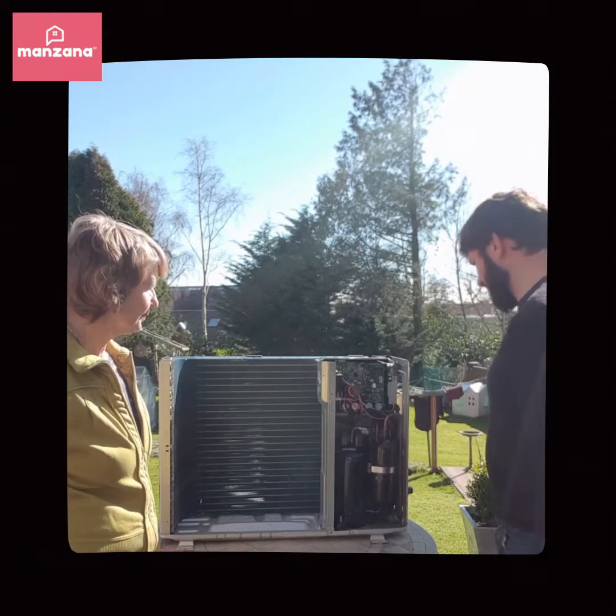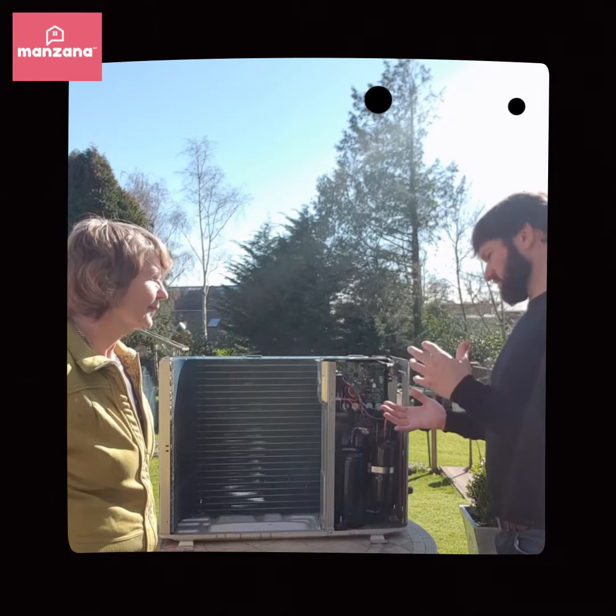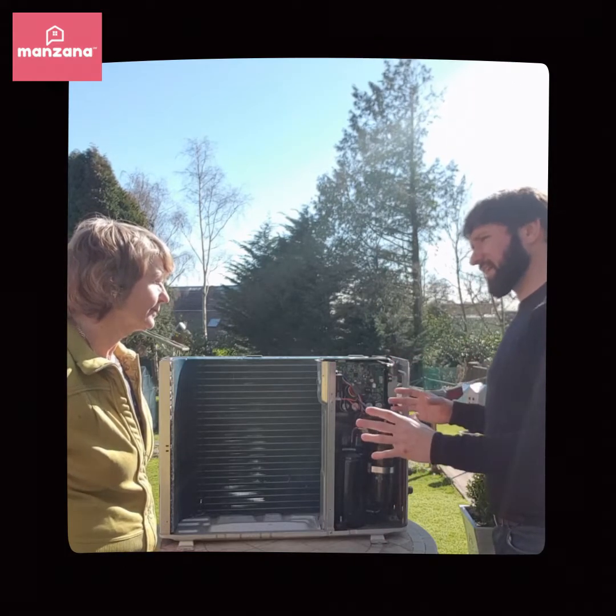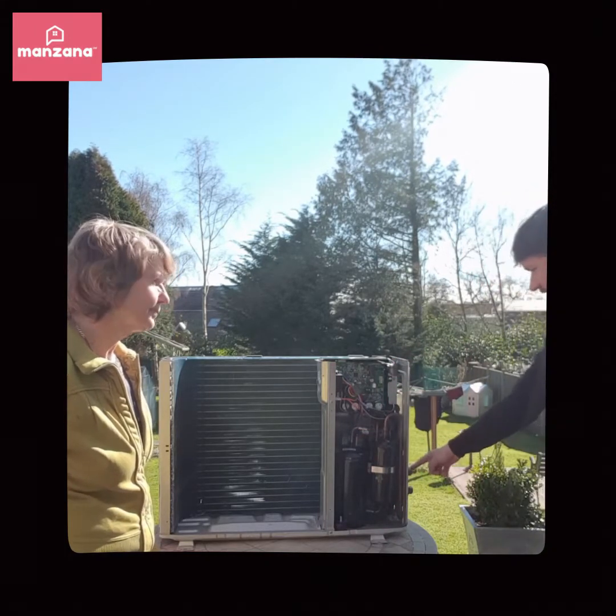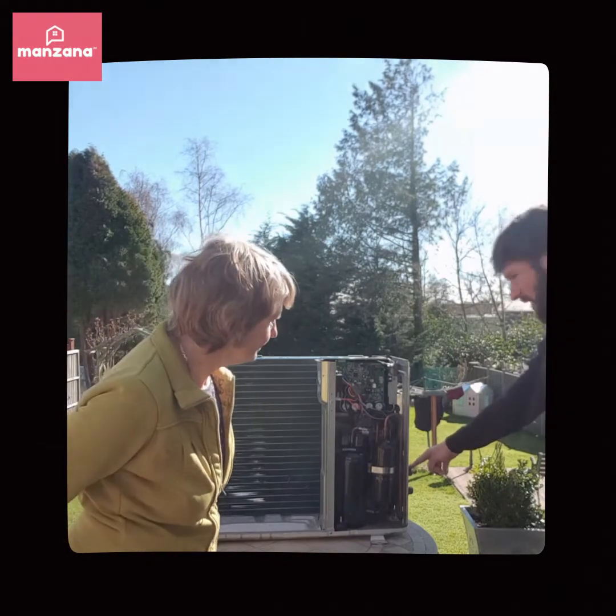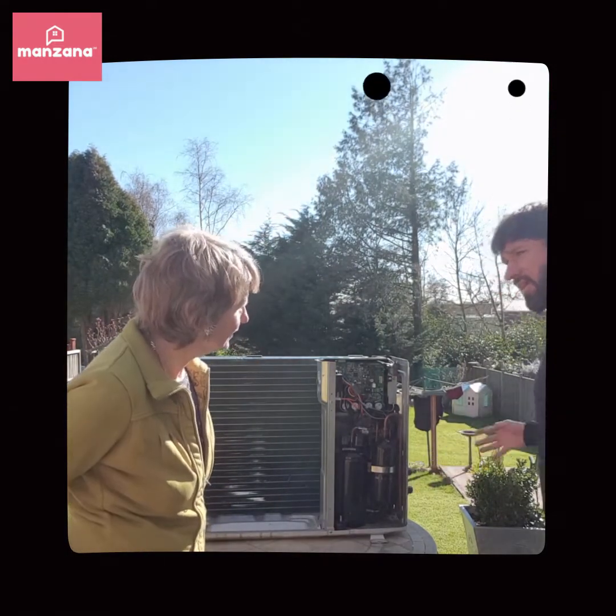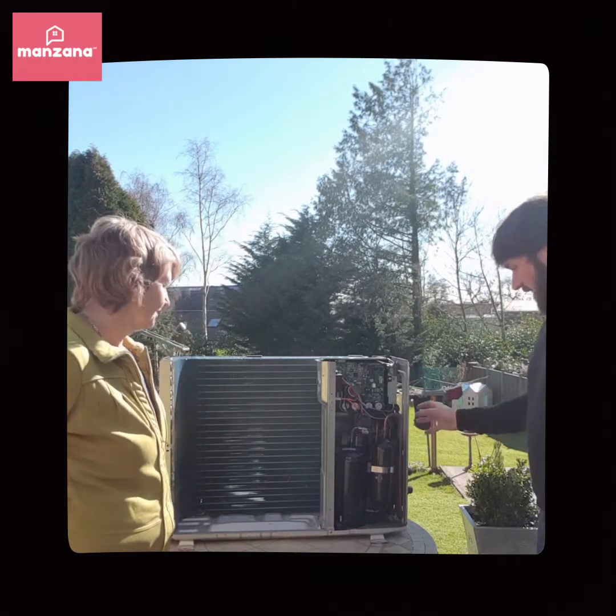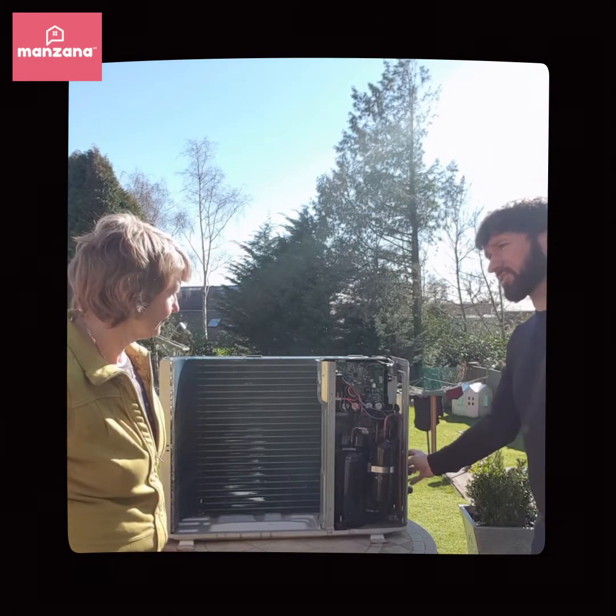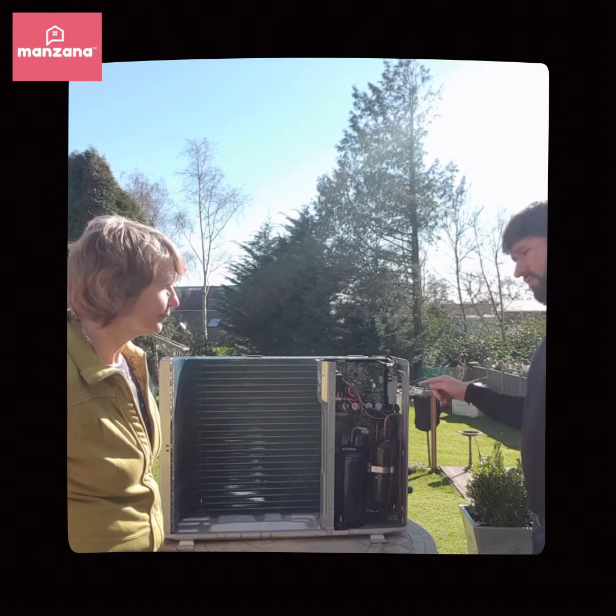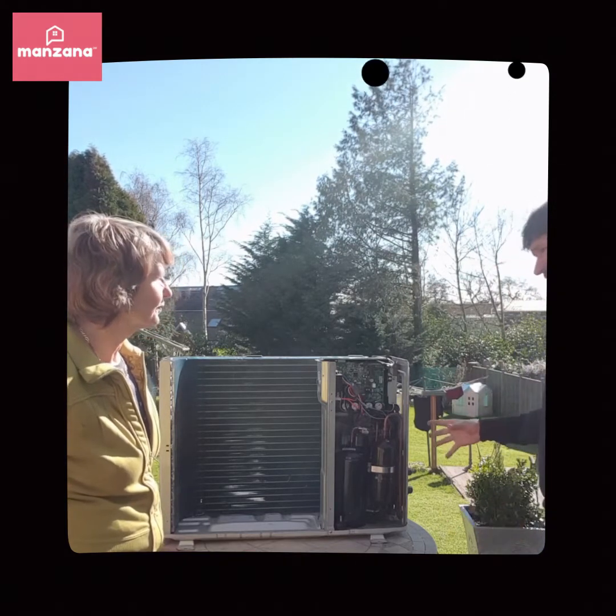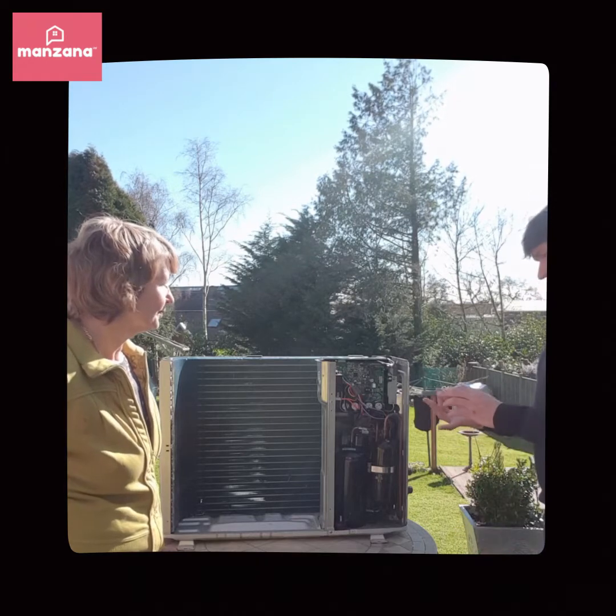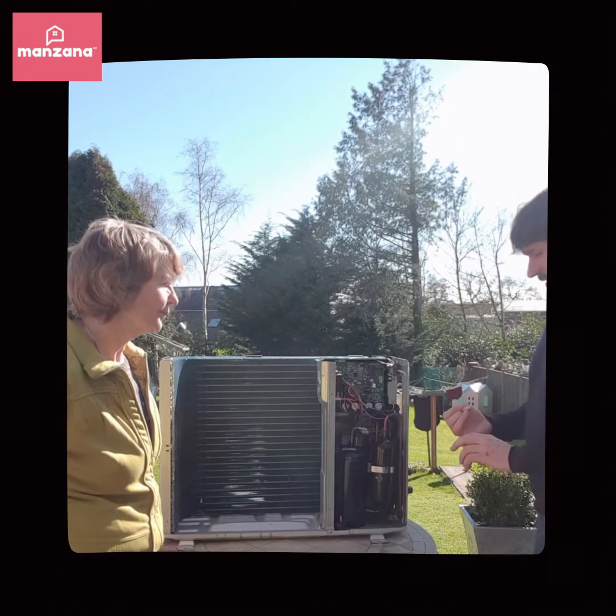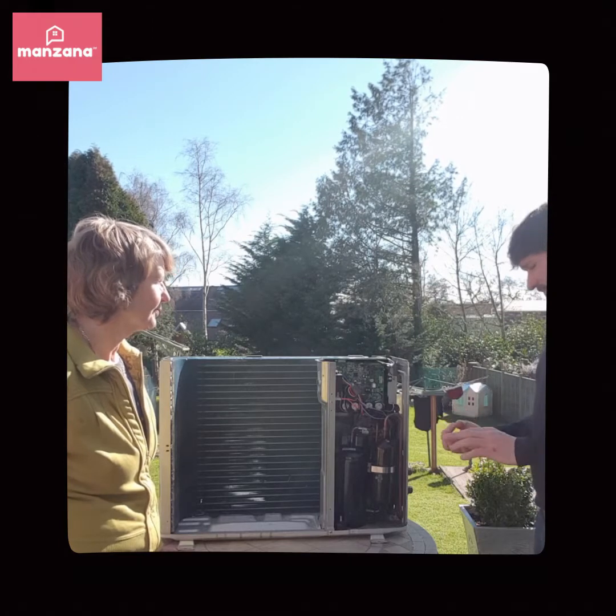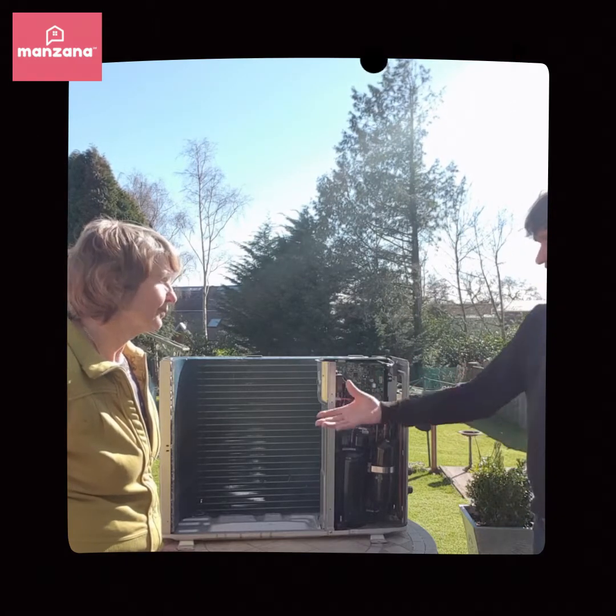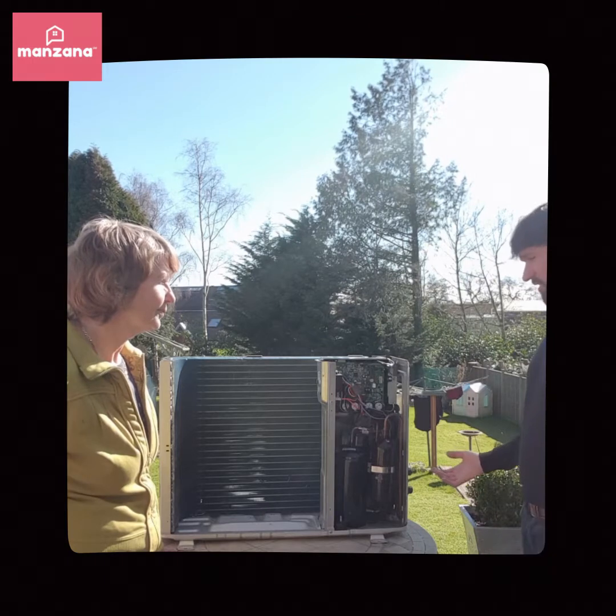This is actually an air conditioning unit, but the technology you're using in an air to water heat pump is exactly the same. The only difference is that an air conditioning unit will have either hot or cool gas coming out of these pipes and going to an indoor unit. In an air to water heat pump, we'll just have a plate heat exchanger, and we'll have water running one side and hot refrigerant running the other side, and so we heat the water with it. But the technology which is in a heat pump is the same as what is in an air conditioning unit, which is in a chiller, which is in your fridge or your freezer at home.